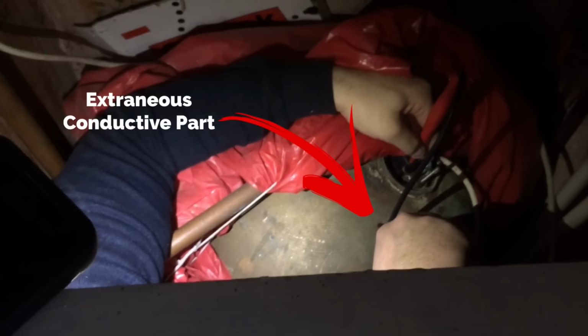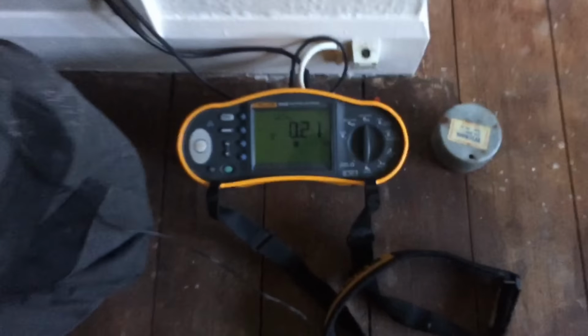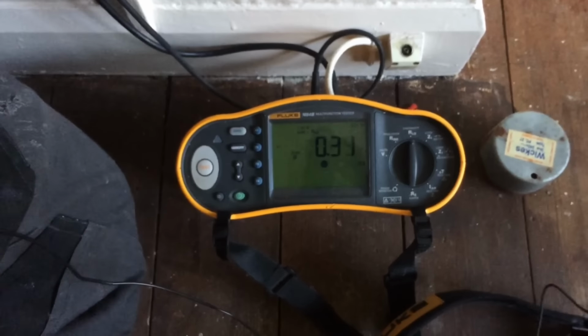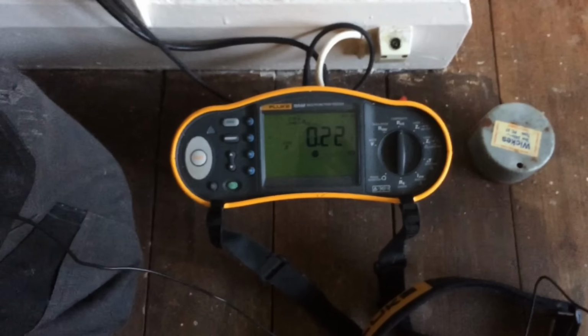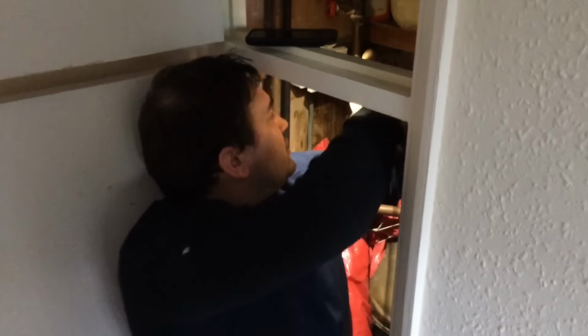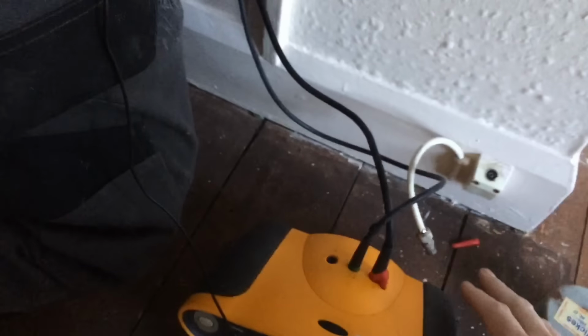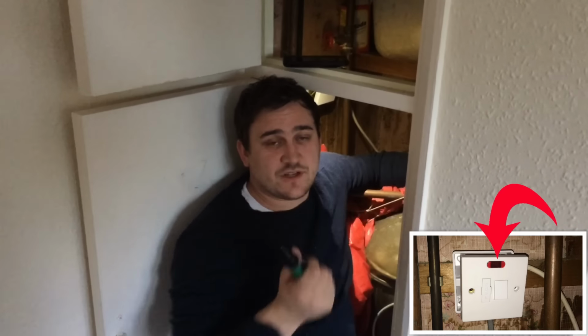Carrying on from our continuity of our circuit protective conductor test, I'm now doing the immersion heater circuit. So I've gone onto the actual tank of the heater for the CPC to prove continuity, and I'm on the line conductor. Get a reading of around, let me give it a scratch, 0.22. Now I'm going to switch the switch to prove polarity. I now have an infinite reading which proves the polarity. In the switch, as it contains a neon, I've disconnected that so it doesn't give me any false readings for my insulation resistance test on this circuit.